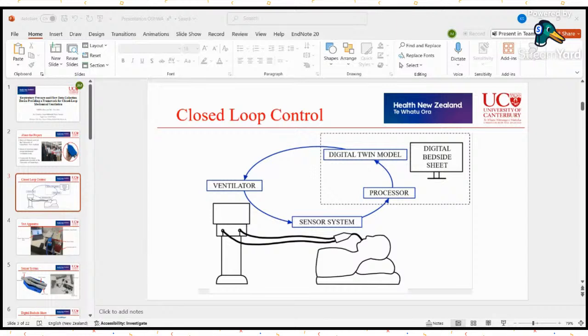Looking at this is how we've been doing our testing. The ventilator is the MEPAT, which I just described, that was designed last year. So that's fully adjustable over Bluetooth. And this is our sensor system in line with a mechanical lung, which is simulating the patient. Our sensor system's measuring the pressure data, sending it via Bluetooth to the portable digital bedside sheet, which is the laptop. All the processing is done in the laptop, and it can send commands back to the ventilator via Bluetooth as well.